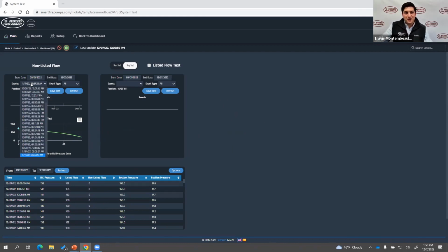So you're talking about data logging there. One of the other things we didn't really touch on is over here, we've got a listed flow test. So if you have that flow meter loop in your pump room and you don't want to flow water through a hose header, you can use a digital flow meter, and we can take that digital signal from that flow meter, capture that data directly from that digital flow meter, plot it against your curve here, and output it effectively for your annual flow test. So now you can have one person running a test instead of two. It really improves your efficiency from that standpoint here.